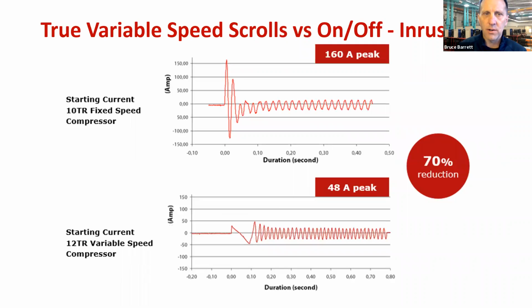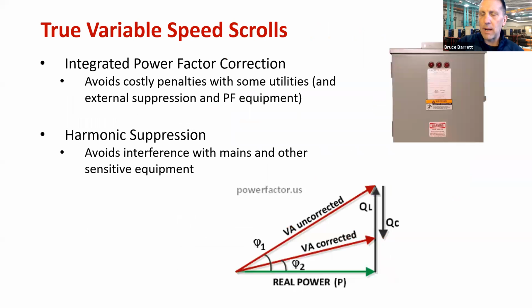This is a little bit of an eye chart. It's actually a 10-ton fixed on top versus a larger 12-ton true variable speed on the bottom, and upwards of 70% inrush savings just by going to that variable speed compressor. Great power factor out of the box, always going to be greater than 0.90. A lot of government facilities require 0.90 power factor or better. You can get that with the true variable speed and some good harmonic suppression. It's about 40–50% suppression out of the box with a standard drive.